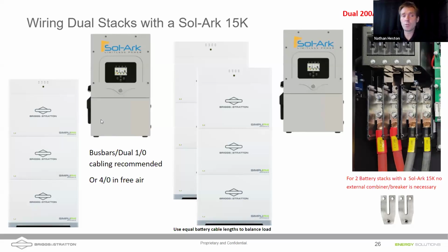We recommend using dual sets of battery cables, two positives and two negatives coming from a single stack. With a double stack setup, use dual sets of cables from a single stack, plus one set of cables from each stack. But you'll be limited to 200 amps DC if you only use one set of cables, since there's a single pole 200 amp breaker on each positive. So to take full advantage of the Sol-Ark, either use dual sets of cables from a single stack, or use the combiners that Briggs and Stratton makes and offers.